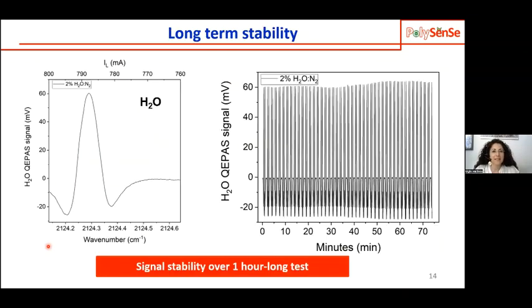We also tested the long-term stability of the sensor. We flowed a concentration of 2% of water vapor through the sensor, and we monitored the absorption peak for more than 1 hour. As you can see, the signal is very stable.